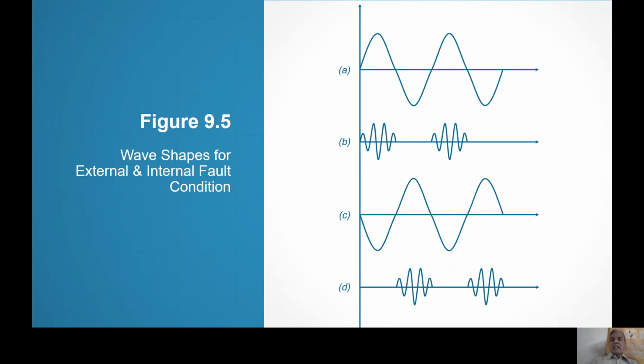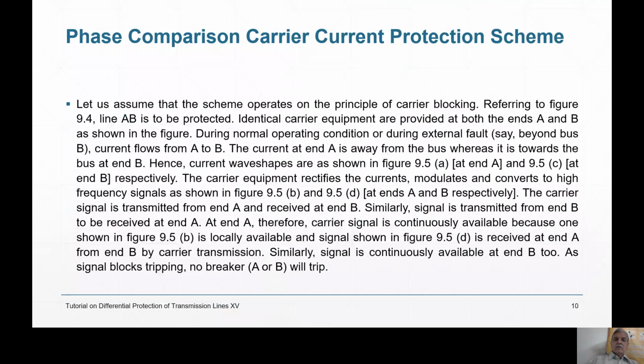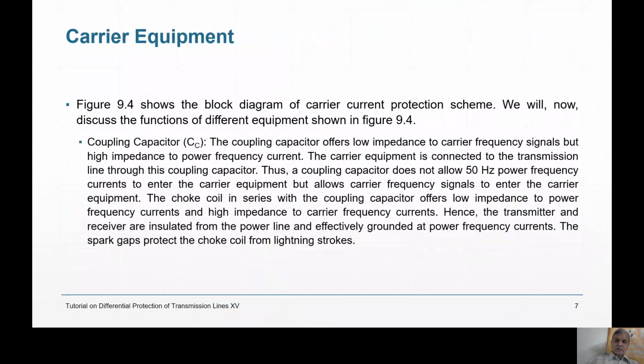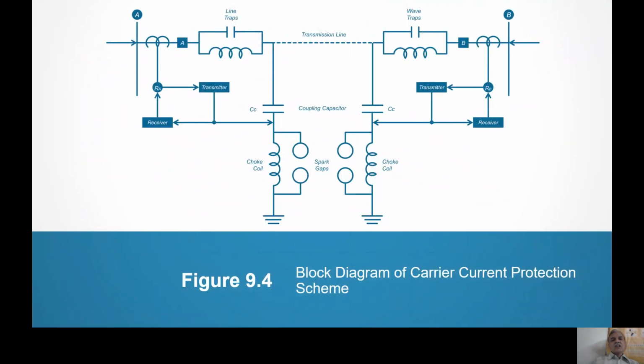Say between line AB there is a fault. Sorry, there is no fault. Let us take first the case of no fault or an external fault. Then current flows from A to B. So for the CT at A, current is flowing away from the bus, and at B it is flowing towards the bus.